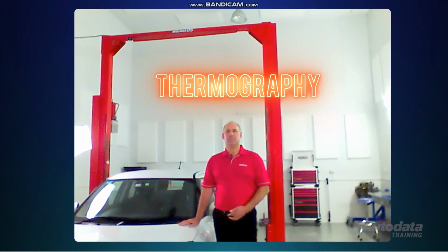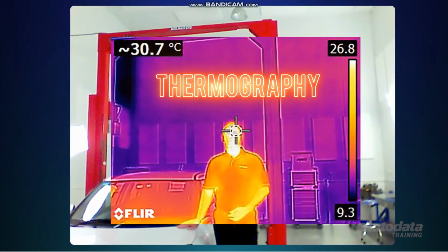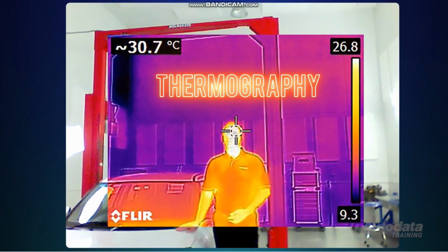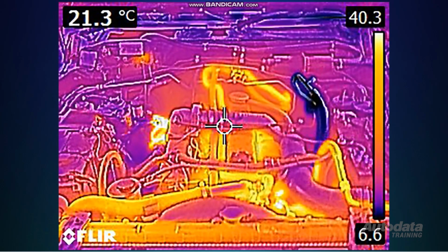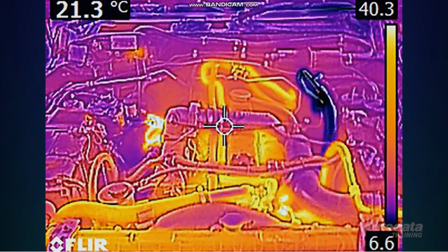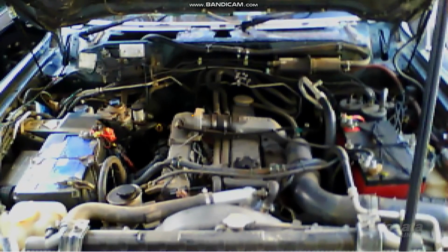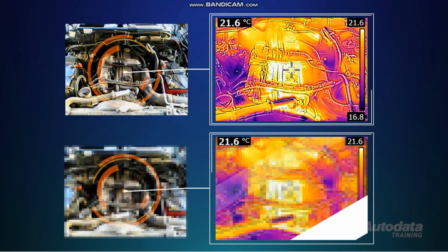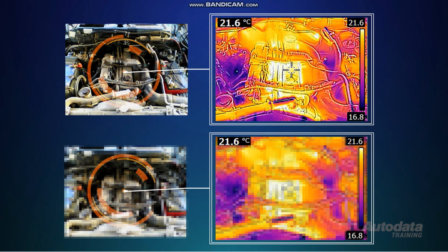To actually see any of this radiation, we use a process called thermography, which transforms an infrared image into a radiometric one with an infrared camera. These cameras display temperature measurements across individual pixels. The finer the radiometric resolution of a sensor, the more sensitive it is to detecting small differences in reflected or emitted energy. Resolution is more important in infrared imaging than it is in digital photography, because it directly affects the accuracy of temperature measurement as well as image quality.